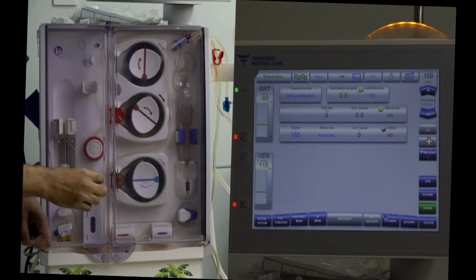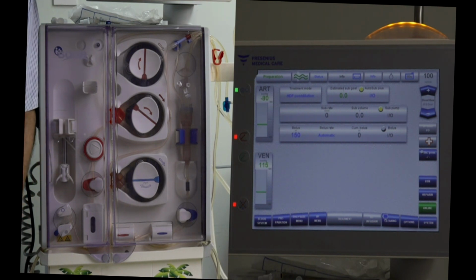When I choose auto sub function, the machine will adjust the replacement fluid rate, monitoring the transmembrane pressure and the fluctuations in the venous pressure caused by the peristaltic pump of the blood tubings. As a protein layer forms over the dialyzer fibers, the pressure fluctuations will become attenuated, and the machine will use this to gauge the amount of clogging of the membrane of the dialyzer and adjust the substitution fluid accordingly, while maintaining the transmembrane pressure within a range of around 250 millimeters of mercury.